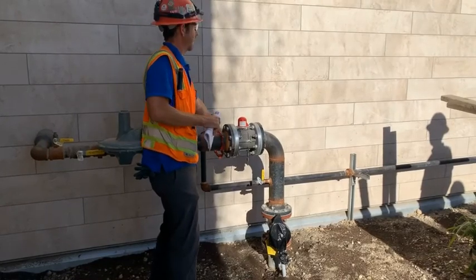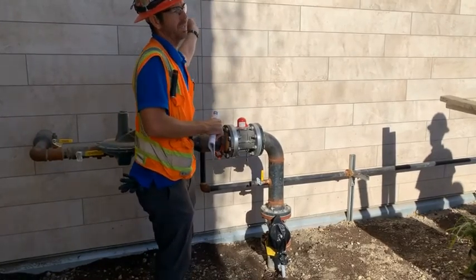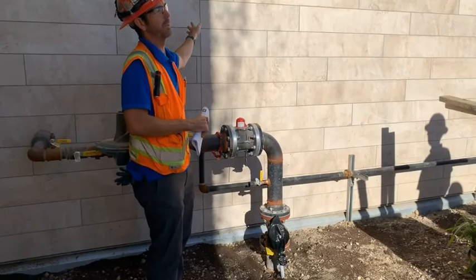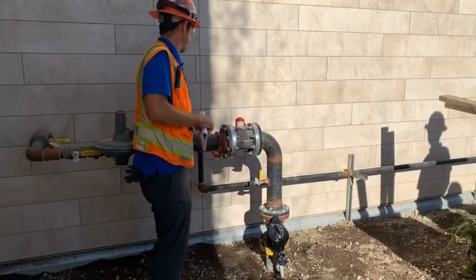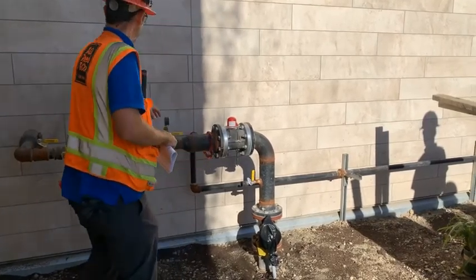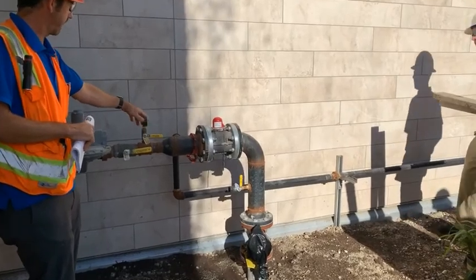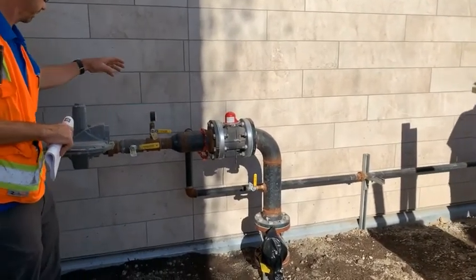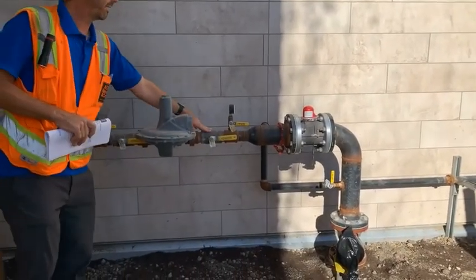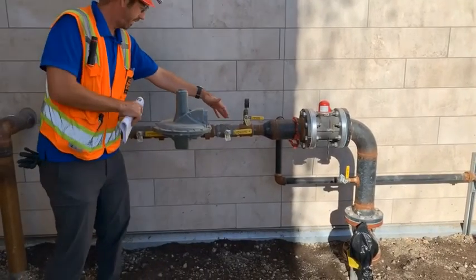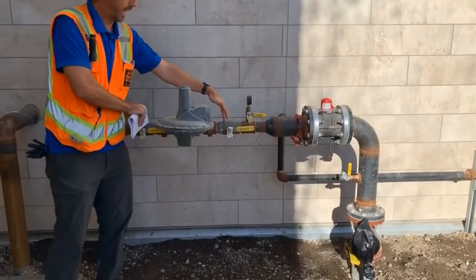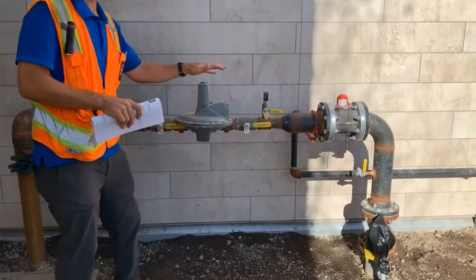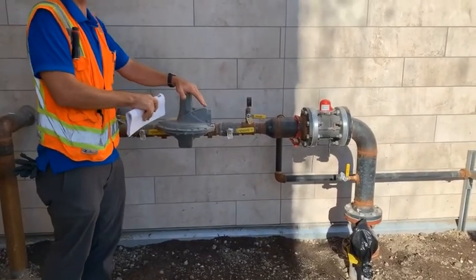We have a medium pressure gas line that runs into the building that feeds the boilers. And when we get inside the building, I'll show you that. So that's this line right here. Down from here, we have a test gauge right here. You can measure the inlet pressure. Then we have a shutoff valve. This shutoff valve, obviously the 2 in and out will isolate your regulator. This is your medium pressure to low pressure gas regulator.